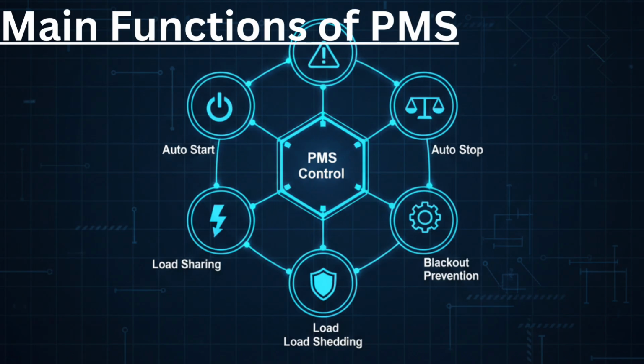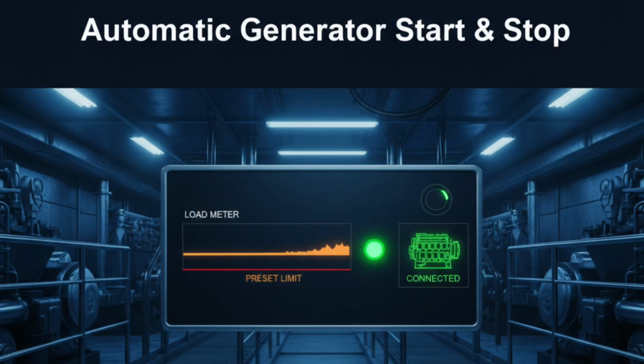During load sharing, PMS ensures that all generators contribute evenly, preventing overload on any single machine. In case of overload or frequency drop, it performs automatic load shedding, ensuring that essential equipment like steering gear, fire pumps, and navigation lights remain operational. Modern PMS systems also provide alarms, historical logs, and predictive alerts, enabling engineers to proactively manage potential faults before they cause serious issues. Automatic generator start and stop is one of the most important features of PMS.